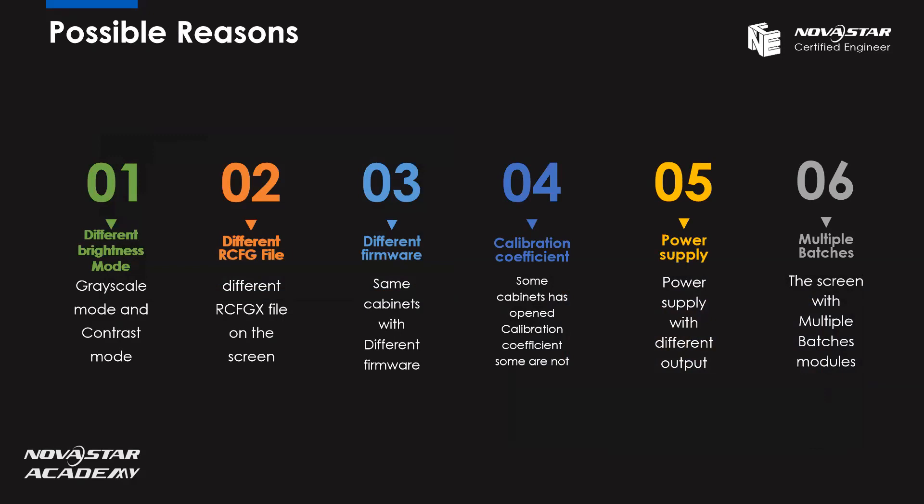I've prepared six possible reasons for you. First, different brightness modes. Second, different RCFG or RCFGX file. Third, different firmware program. Fourth, calibration coefficient. Fifth, power supply. Sixth, multiple batches. All of them can influence the brightness effects on the screen. Let's look at them one by one.